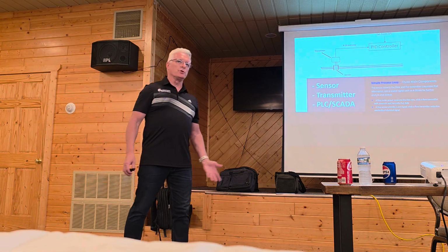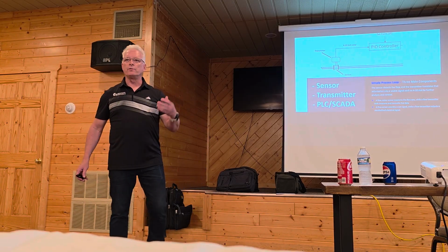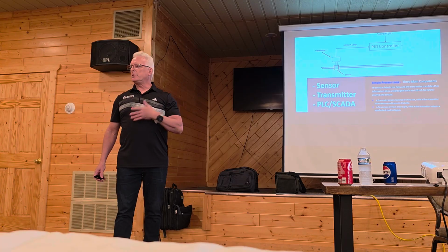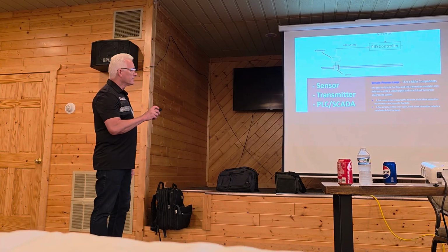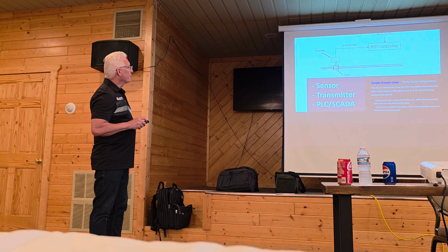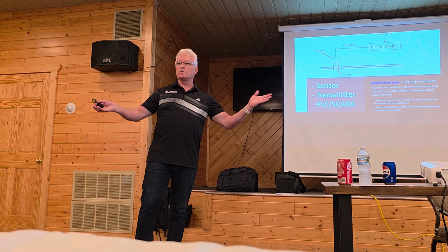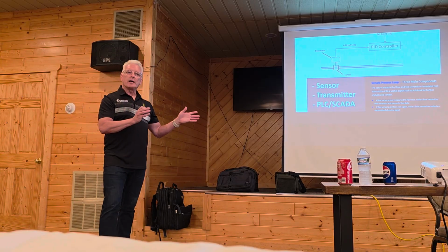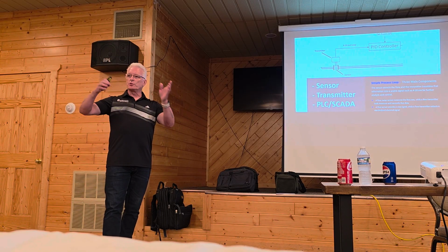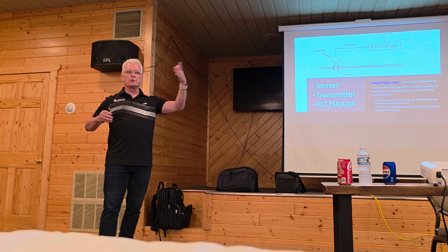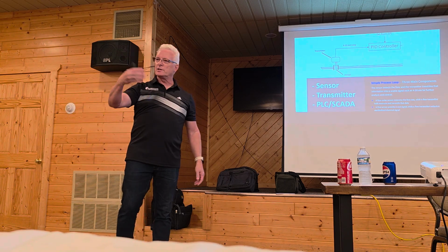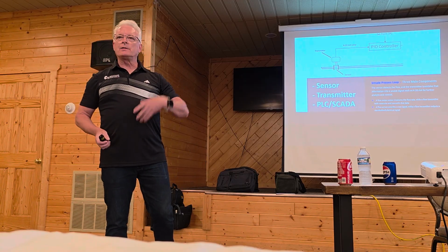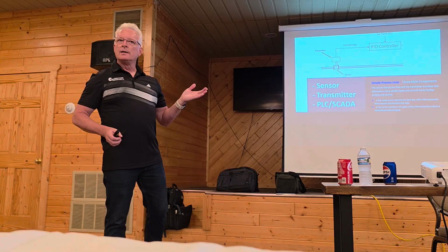So what do these instruments do? So the instrument reads the real world variable, we call it a process variable, whether it's water, flow, temperature, conductivity, pH, whatever it is. So it reads that. And then once it reads, so this is, say, a flow meter, and this is the sensor, this is the transmitter. And then once it figures out what that is, it translates that into a 4 to 20. So if you're saying it's 0 to 1,000 gallons per minute, that 4 to 20 would now be calibrated 0 to 1,000 gallons a minute. And so would your PLC, and so would your SCADA, whatever it's going to, so everything's the same going through. It's like speaking English and you can understand it. If it's not, then it's not going to read it right, it's not going to trend it right, it's not going to totalize it right.